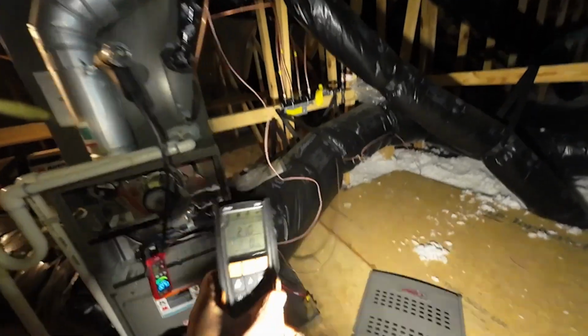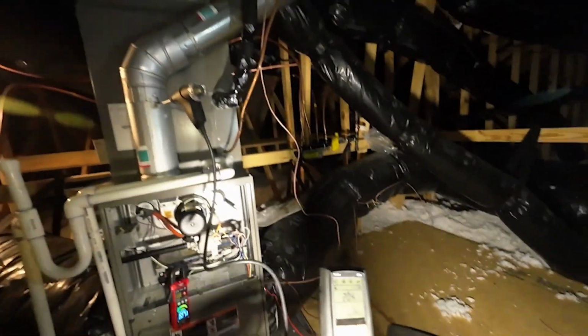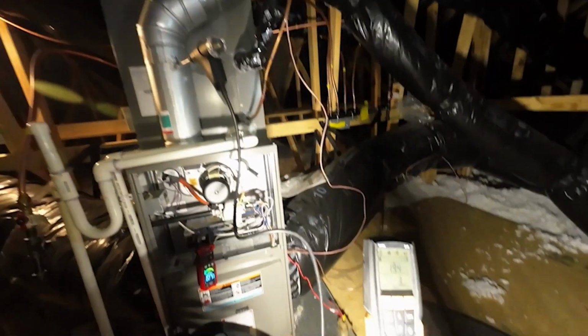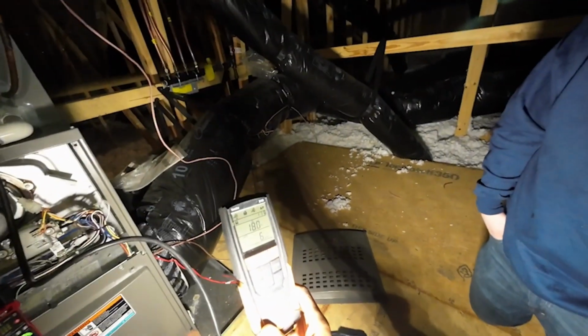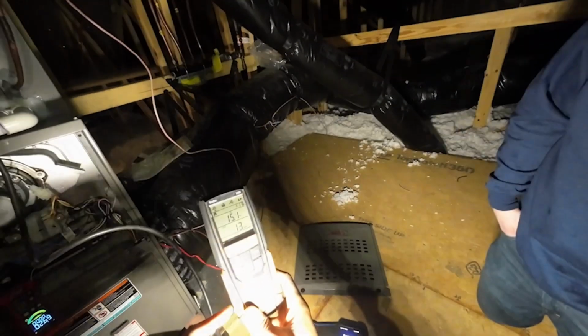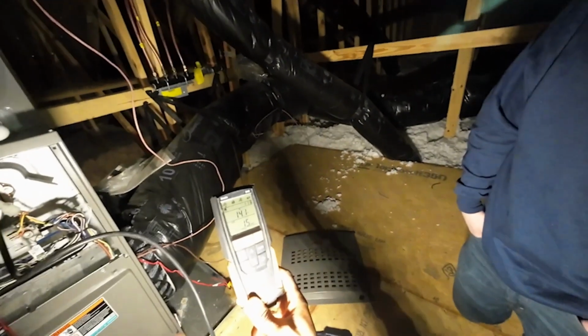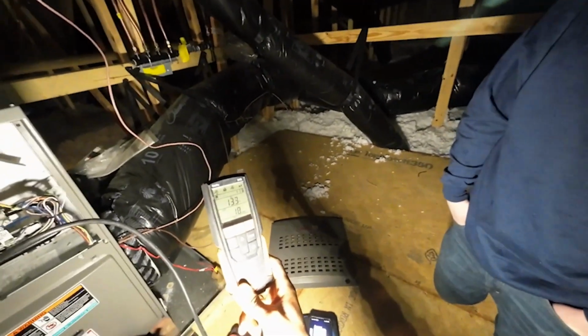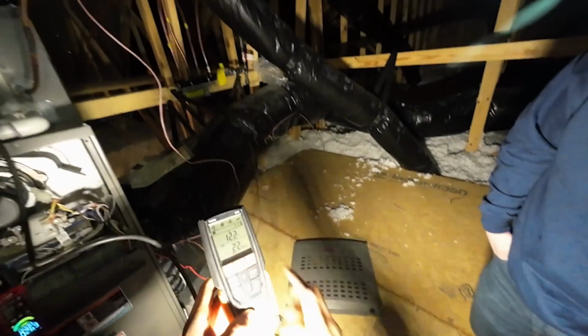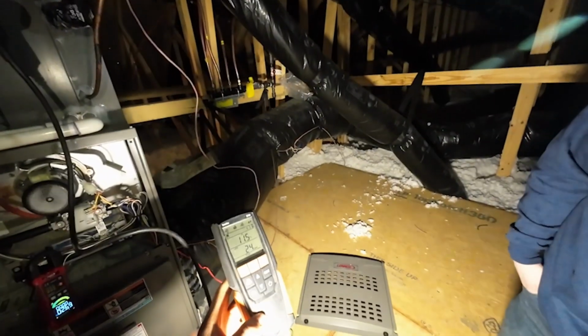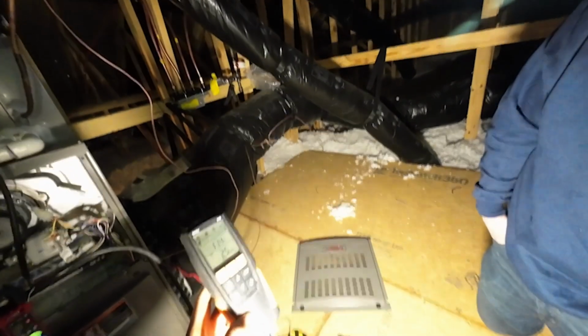Hit start, and we're wanting to see O2 is oxygen. That means how much oxygen is in these gases, right? Mm-hmm. Pure oxygen. You want that to be between maybe 5 and 9%, something to that effect. CO, that's going to be carbon monoxide. That's going to be a deadly gas. I know you've heard of that. Oh yeah. So we want that to be below 100 parts per million.